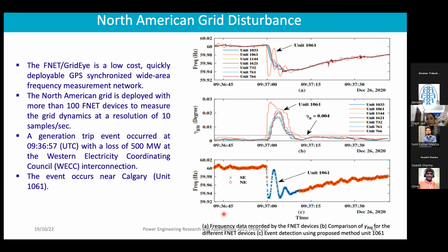Now, basically, when we had verified it on Indian power grid measurements, it was important to see its performance on some other grid also, because different power grids exhibit different characteristics. So it was a North American grid disturbance, where they have deployed FNet or GridEye, which is a low cost, quickly deployable GPS synchronized wide area frequency measurement network. These data were available on the website, and they have deployed around 100 FNet devices to measure the grid dynamics at a resolution of 10 samples per second. So we are considering here only a slow event.